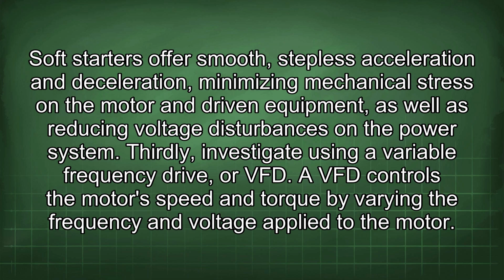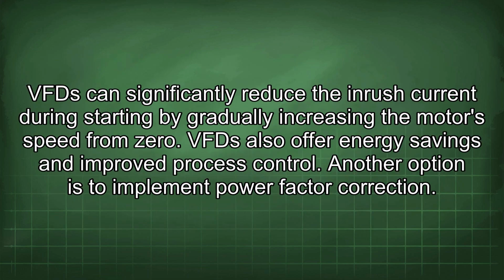Thirdly, investigate using a variable frequency drive, or VFD. A VFD controls the motor's speed and torque by varying the frequency and voltage applied to the motor. A VFD can significantly reduce the inrush current during starting by gradually increasing the motor's speed from zero. VFDs also offer energy savings and improved process control.